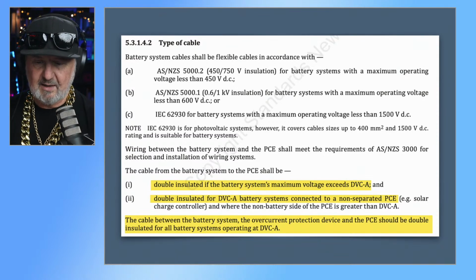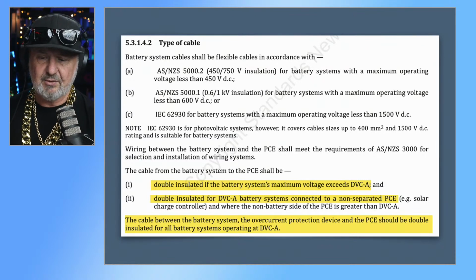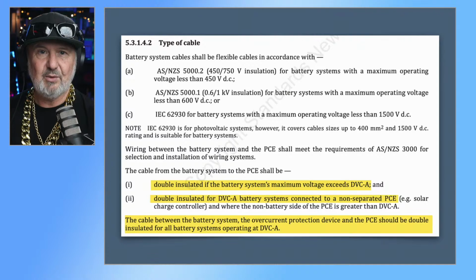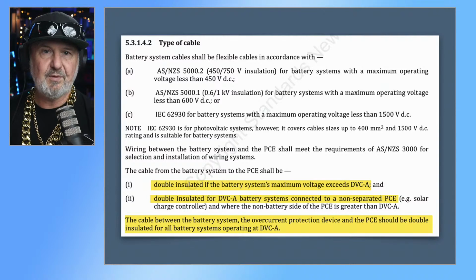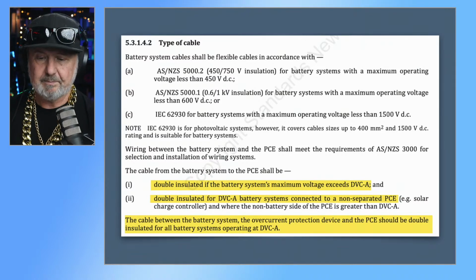Just seeing a bit of chat here. Shepsy says, Glenn, around AC isolation, there was some greyness around groups of inverters, for example multi-mode inverters creating 3-phase where inverters are spread across several meters. Yes, so that's exactly the situation we have. And as I said, if there are distances greater than 2 meters from the battery or any one of those inverters, you need to have isolation adjacent to each one of them. And additionally, which kind of overrules that clause, if you've got more than one PCE, each one needs its own isolation. So yeah, a 3-phase system made up of 3 single-phase inverters, isolation for each of them.